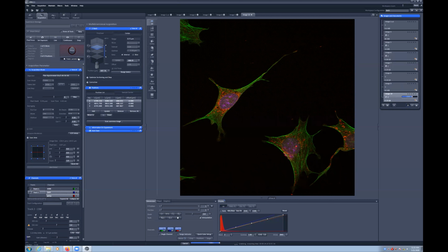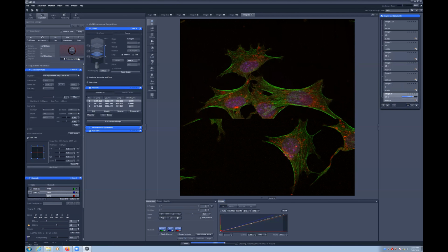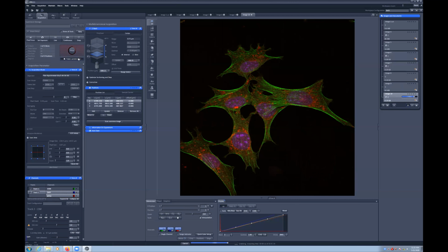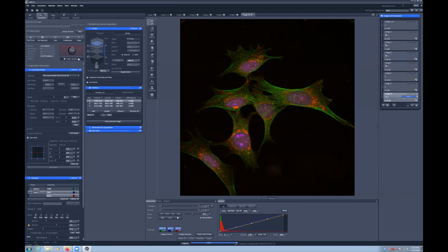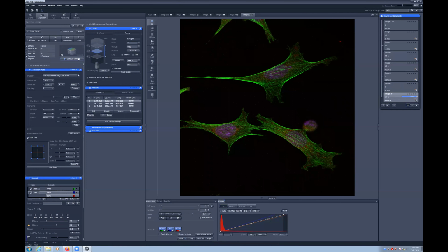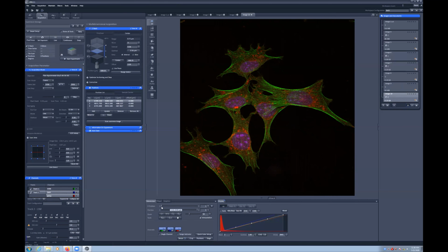One important thing to remember with both tiling and positions is not to move too far around the cover slip if you are using an immersion objective, as you may end up smearing the immersion too thin and damaging the objective. Talk to facility staff about alternate options available for your captures.